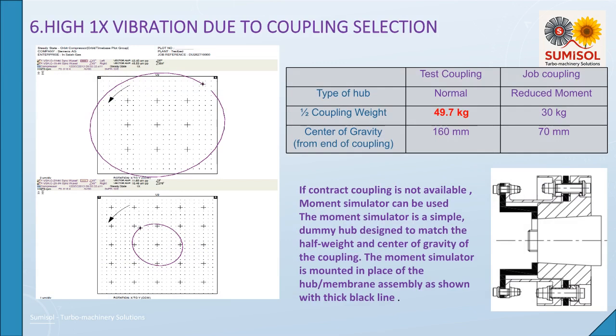It was noted that during the test a shop coupling was being used instead of the specific job coupling. Comparison between the test coupling and job coupling is shown in the picture on the right side. The overhung weight of the test coupling is significantly larger than that of the job coupling. The rotor dynamic check showed that the rotor with the shop coupling mounted is likely to become thermally unstable. The rotor with the intended job coupling mounted is calculated to be thermally stable. The test was conducted with the contract job coupling after a few weeks, and vibrations were much below API acceptance criteria.